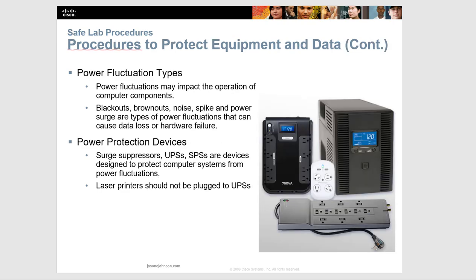With power fluctuations, all devices need power and there are different types of fluctuations. A blackout is a complete loss of AC power, caused by a downed power line or blown fuse. A brownout is reduced voltage — it occurs when the power line voltage drops below 80% and can cause problems with electrical circuits. Electrical noise is interference from generators or lightning, producing poor quality power and causing errors in computers. A spike is a sudden increase in voltage, often caused by lightning strikes or when an electrical system comes back on after a blackout.